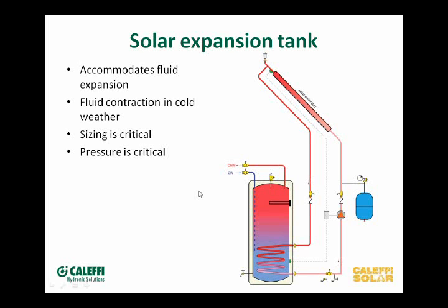I ran a calculation on a system that had 90 gallons of solar fluid in it — it required a 40-gallon expansion tank. The collectors held about a gallon and a half each and there were quite a few of them. That's the size of a typical water heater just as an expansion tank. The tank has to be able to handle a much bigger volume of expansion.